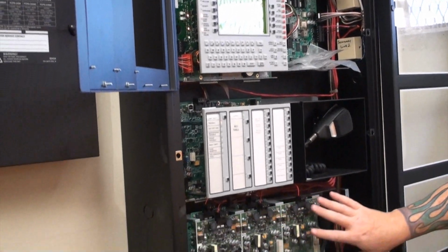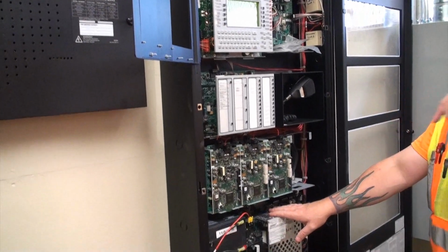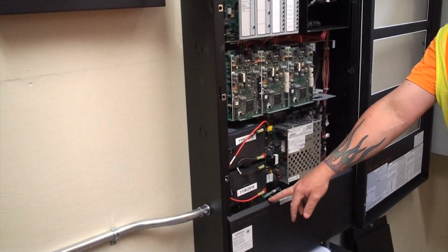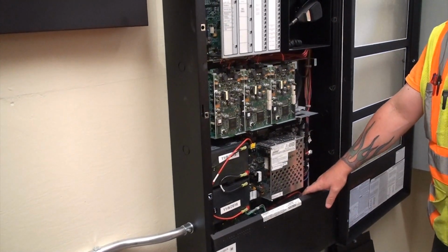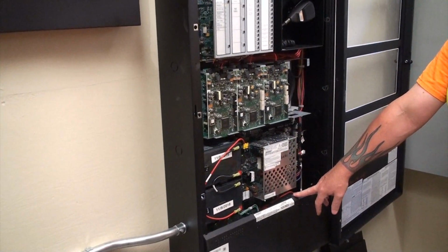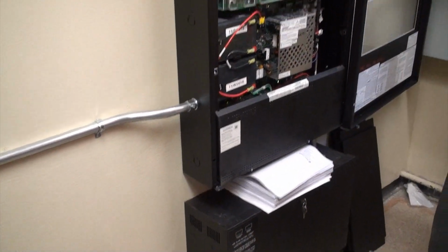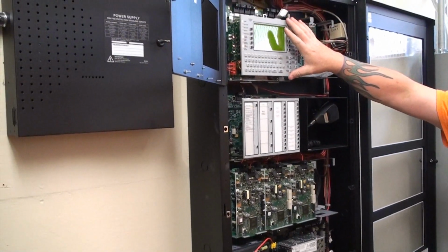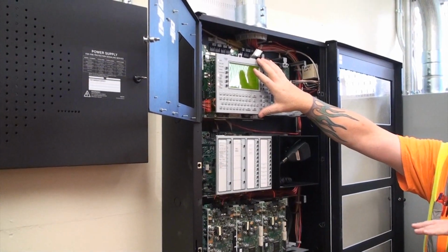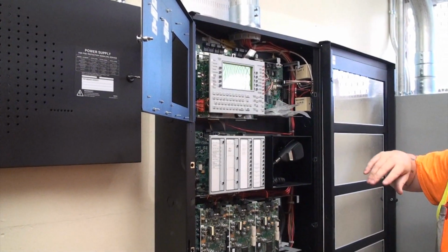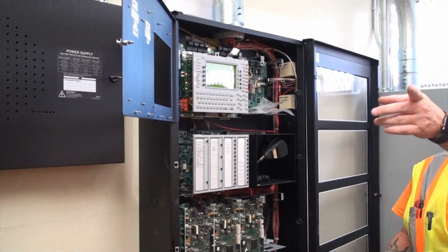Then we have all your loop cards for this panel. Your amplifier is going to be for this building. You have your main power supply, and then we have an ACPS, which is an auxiliary power supply. This is where your triggers are getting fed from. You have your batteries that are down here. This one you'll only see off of this display just the buildings off of this node. And the other one, it'll say something like node 2, the NCA, you'll see everything, which I'll show you in a second.